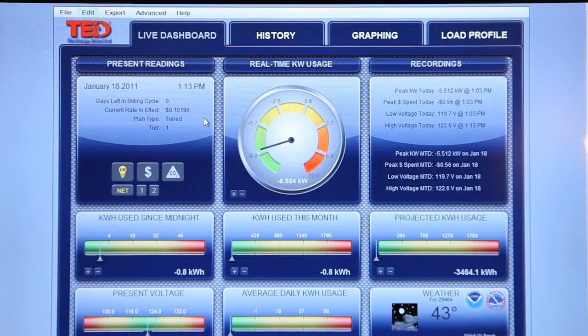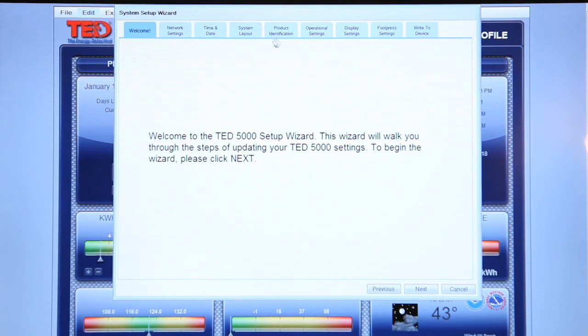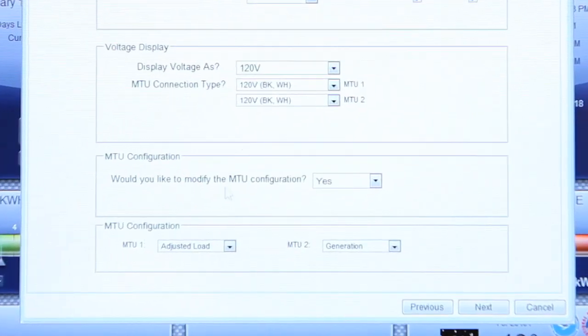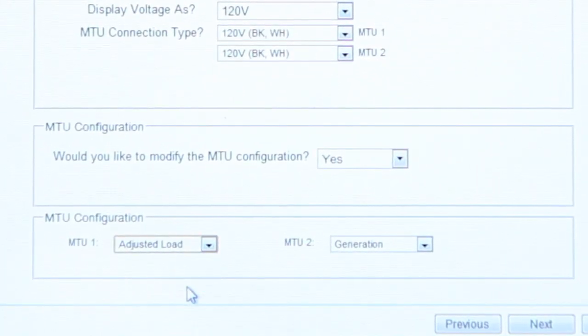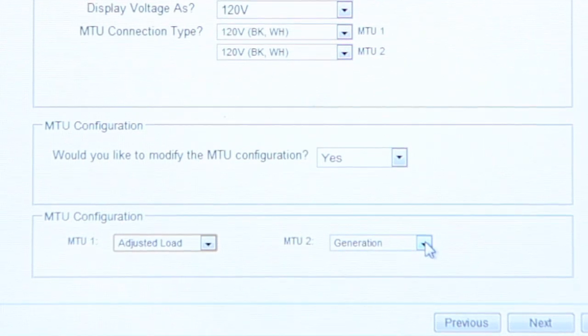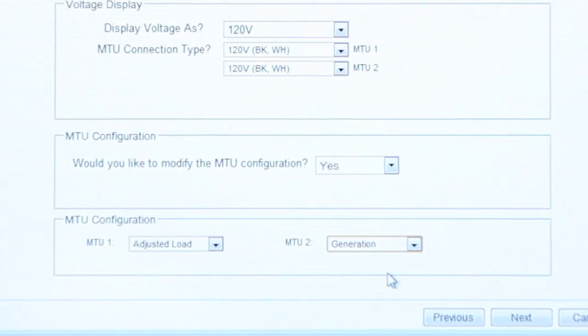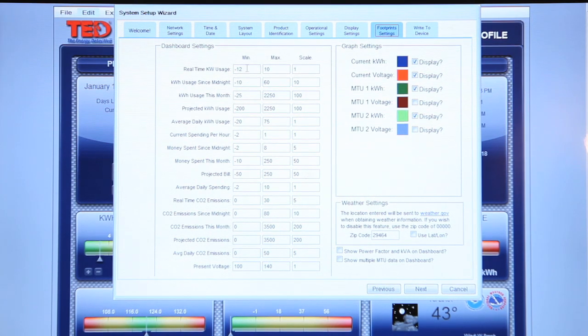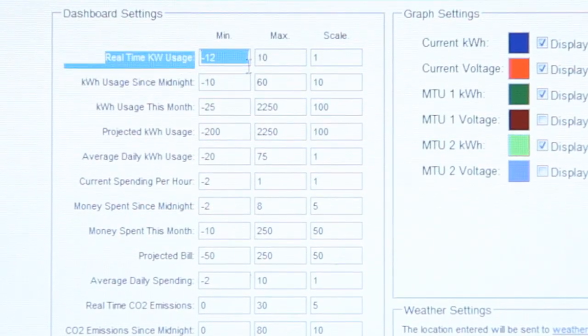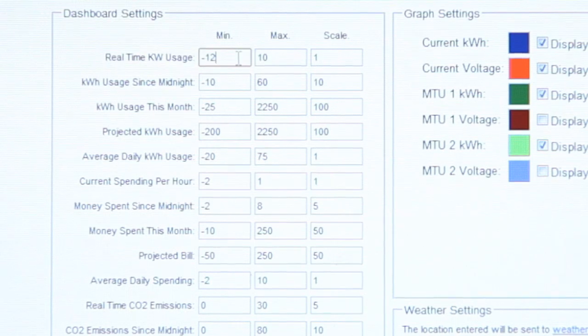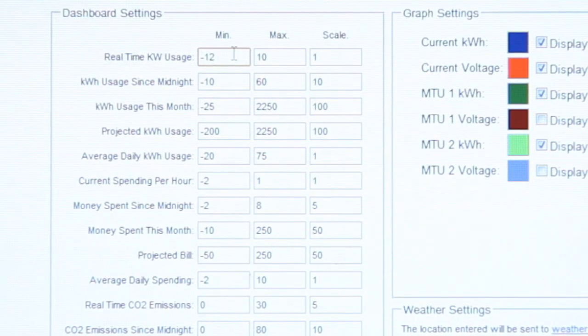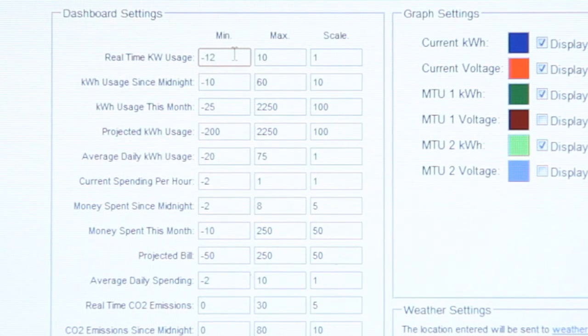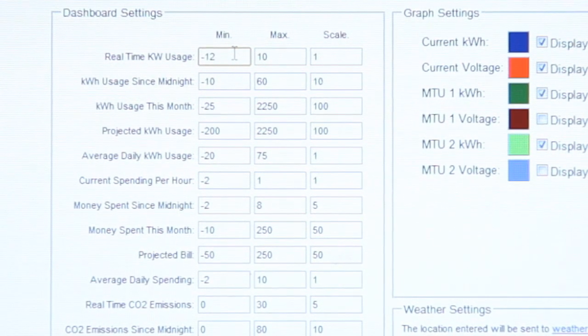The settings for this configuration in the system settings wizard are as follows. MTU 1 is set to adjusted load, so that it will show the direction of current flow to or from the power grid. MTU 2 is set to generation. For all generation setups, you will want to change the minimum real-time kilowatt usage to a negative number. The negative number should be the maximum amount that your PV, wind, or solar installation will produce. In our example, we use negative 12 since our generation could be as much as 12 kilowatts.